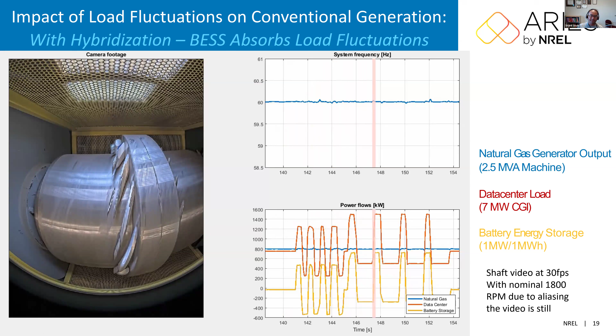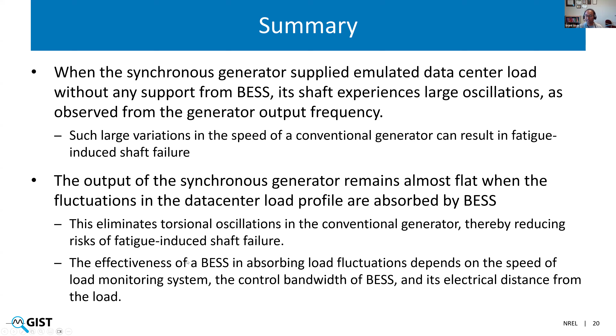The storage could be within IT racks, at the point of interconnection behind the meter, or within the UPS, which I'd think would be more efficient because you're in a way firewalling the grid from the load. But the main consideration is how fast you're able to measure the load fluctuations and mitigate those.